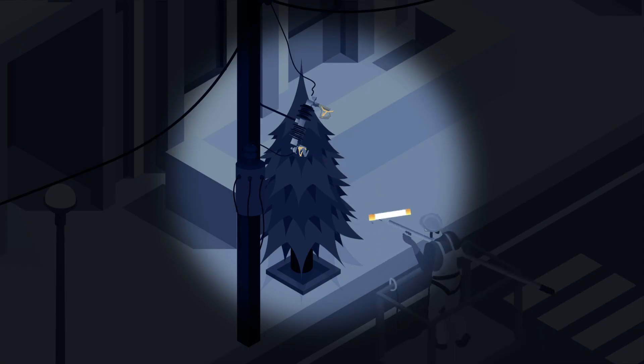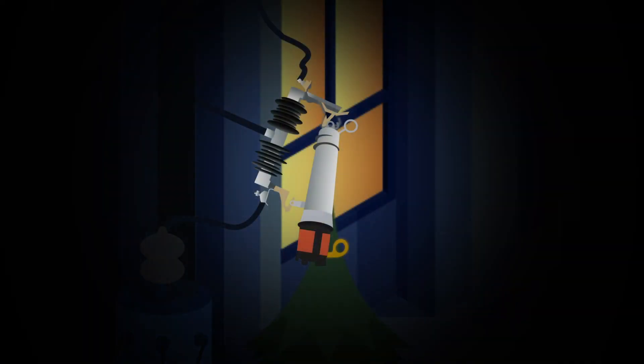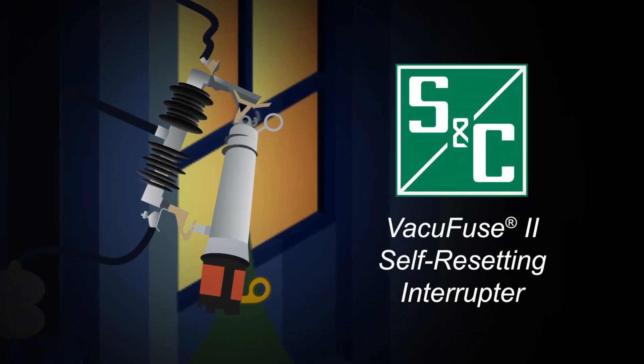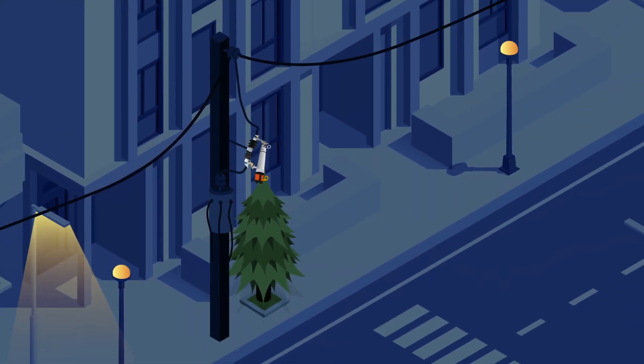It's clear these persistent trouble spots need a permanent solution, but what can be done about them? S&C found a better way to protect your overhead distribution transformers. It's called the VacuFuse 2 Self-Resetting Interrupter. It tests whether or not faults are temporary, and if they are, it restores power automatically — avoiding a costly truck roll for you and keeping the lights on for your customers.